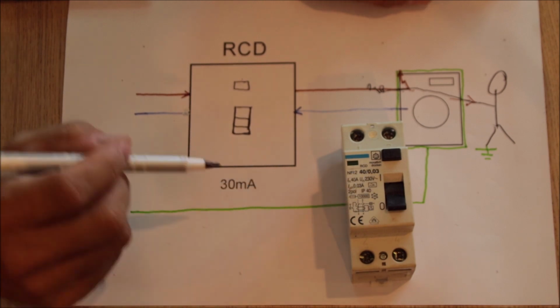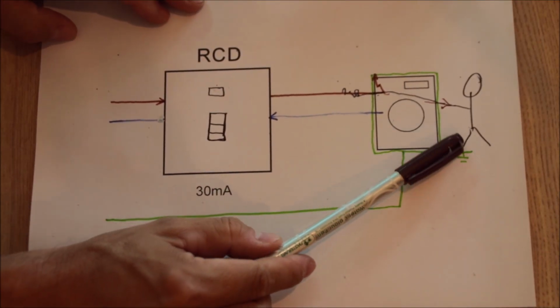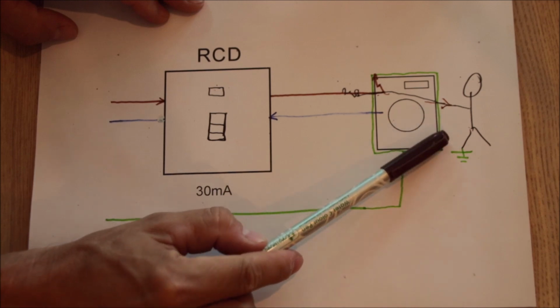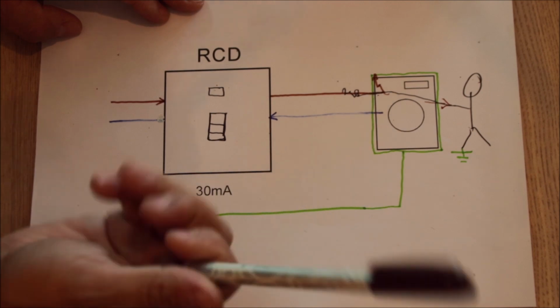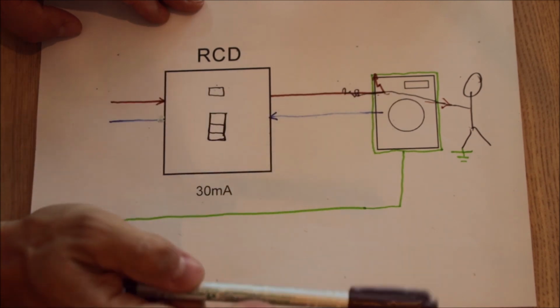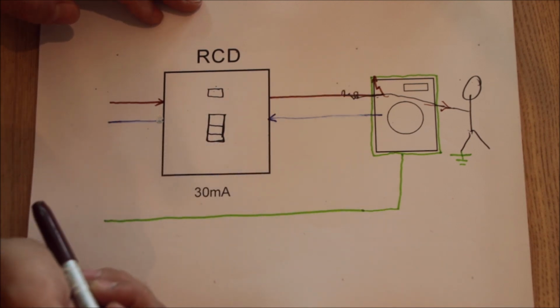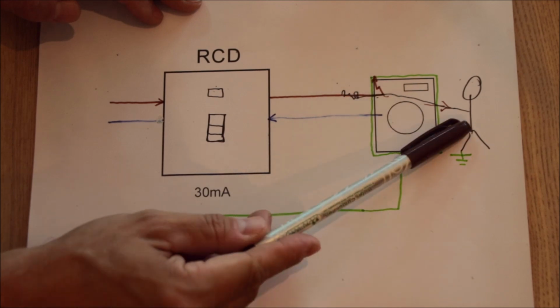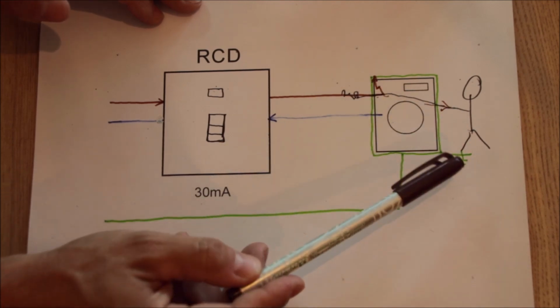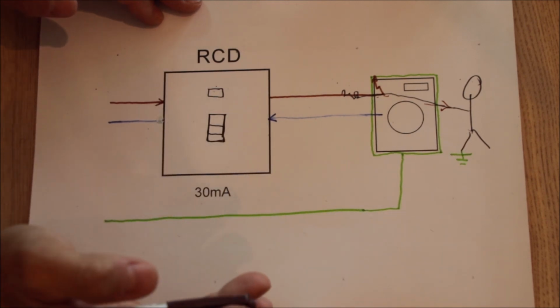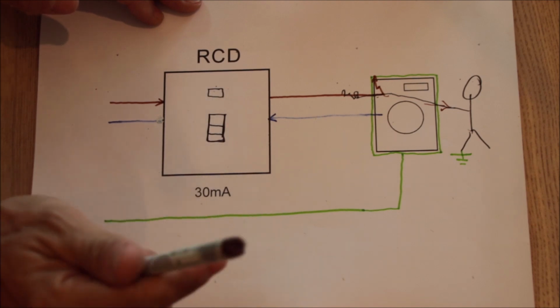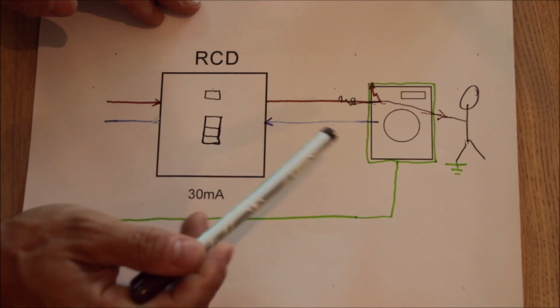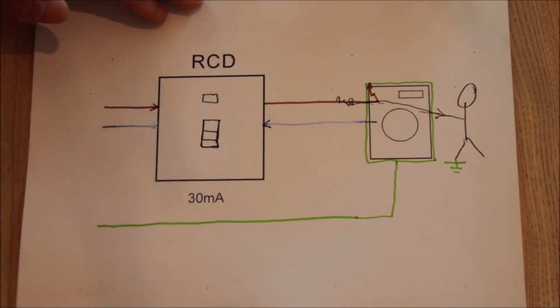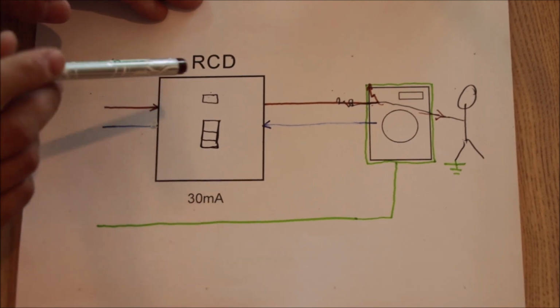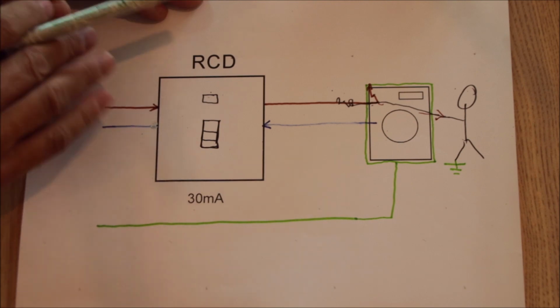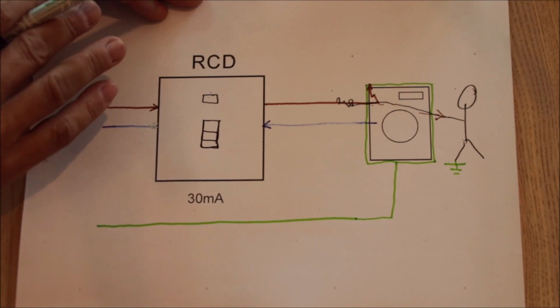greater than 30 milliamps. So humans typically have an internal resistance as everything else. In the worst case, that might be around 300 ohms. If you have a sweaty hand and you take a firm grip on a cable, any surface which is under high potential, you will cause current flowing through your body which might equal somewhere around 1/10 of an amp, or maybe up to 1/4 of an amp. So that current will be missing here on the neutral because it goes somewhere around here, and this will cause the RCD to trip. So no earthing protection without an RCD. The first thing which is very important to say.